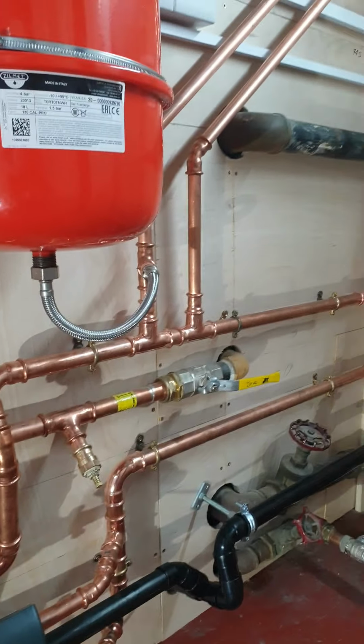So I've put in a backup expansion vessel here for the odd days it freezes, and that forms our new neutral point. That's on our return, and pumps are just on the flow here, and we've fitted on both systems a 3-bar pressure relief valve here. So we've got a secondary sealed system, safety system here, as well as the open vented system. So the pressure at the moment in the system there on that side is going to be about 2.5 bar, probably about 2.5 bar to 3 bar actually, considering the height of the building, and fed by the external tank. The boilers themselves. You can see how busy we were under here.